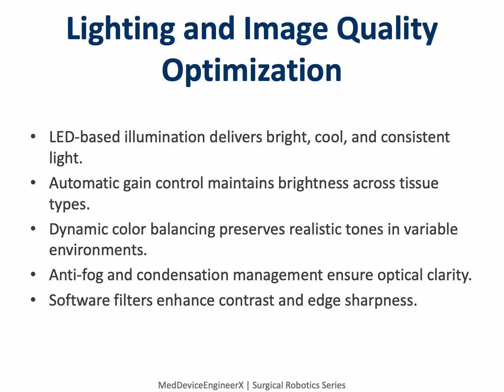Surgical imaging is only as good as its light. Hugo's illumination system uses high-efficiency LEDs that deliver intense brightness without the heat associated with traditional bulbs. The light passes through fiber optics into the endoscope, illuminating deep cavities with uniform coverage. Automatic gain and exposure controls adjust brightness dynamically as the scene changes, from dark tissue to reflective instruments. Color balancing algorithms continuously calibrate hue and saturation, maintaining a natural appearance under all conditions. Anti-fog coatings and active airflow prevent condensation on the scope lens, while digital filters enhance fine structures for visual clarity.